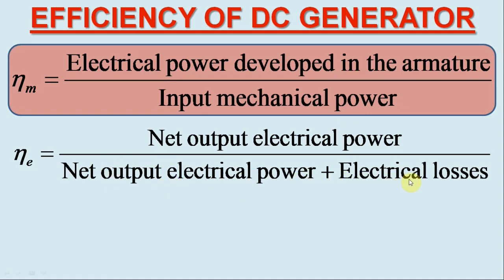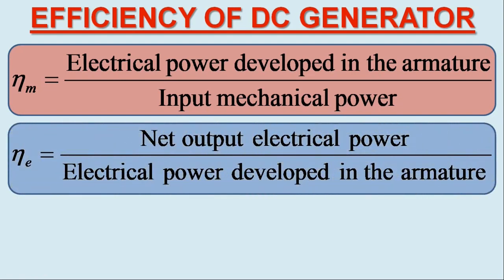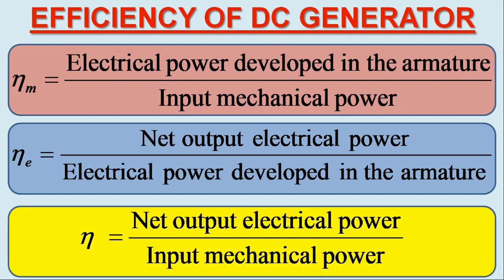The term net output electrical power plus electrical losses is nothing but the electrical power developed in the armature, Eg×Ia. So the electrical efficiency is written as net output electrical power over electrical power developed in the armature. Multiplying these two efficiencies, we may determine the overall or commercial efficiency of the DC generator, which is net output electrical power over input mechanical power.